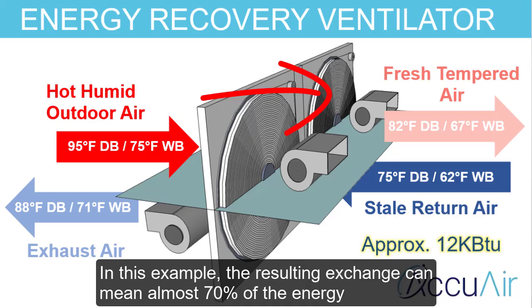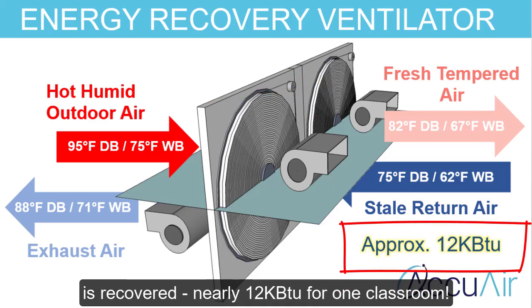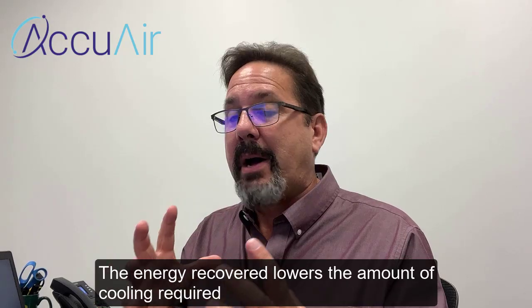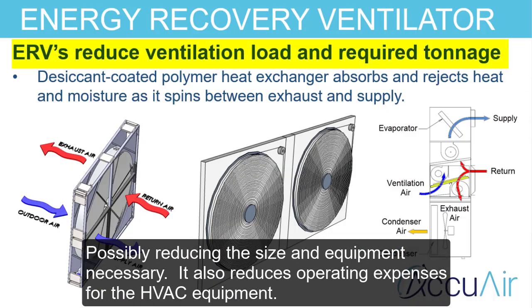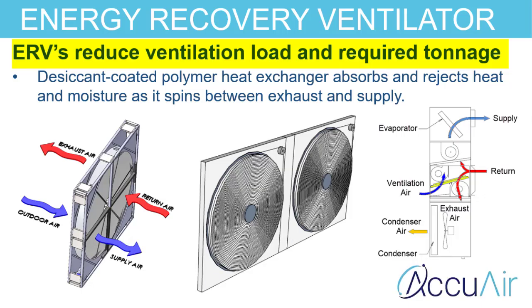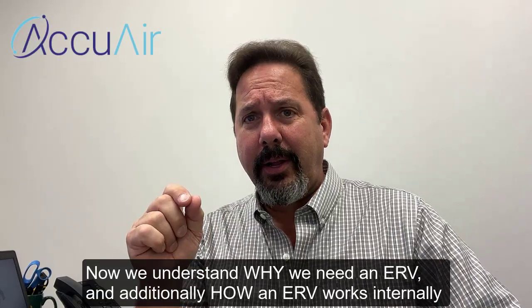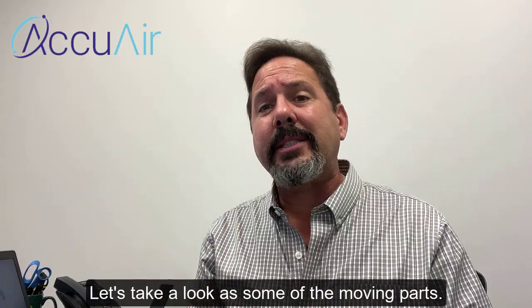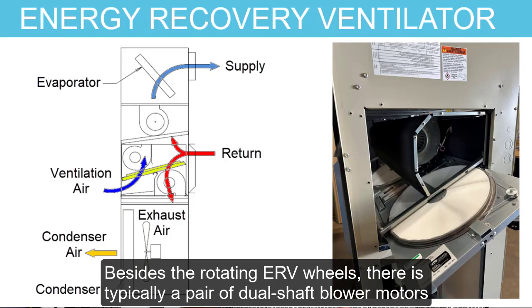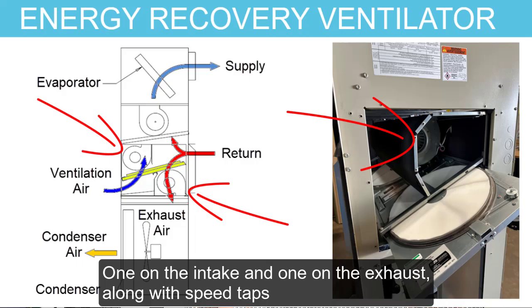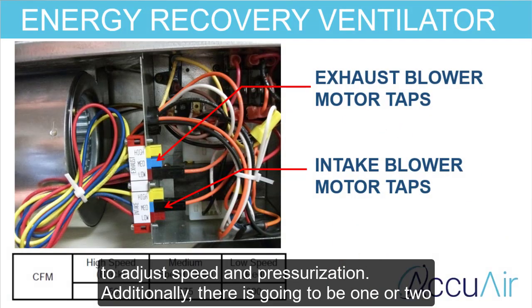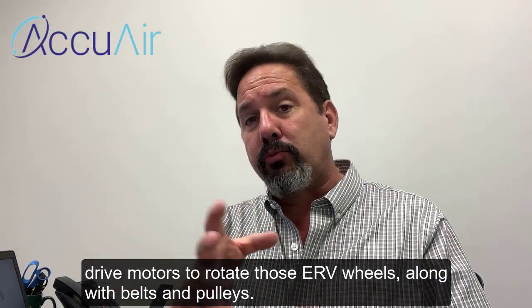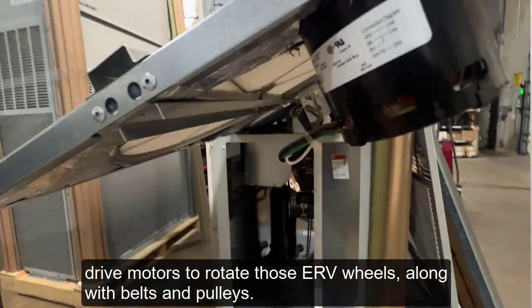In this example, the resulting exchange can mean almost 70% of the energy is recovered, nearly 12,000 BTUs for one classroom. The energy recovered lowers the amount of cooling required, possibly reducing the size of the equipment necessary, and also reduces operating expenses for the HVAC equipment. So now we understand why we need an ERV, and additionally how an ERV works internally. Let's take a look at some of the moving parts. Besides the rotating ERV wheels, there is typically a pair of dual shaft blower motors, one on the intake and one on the exhaust, along with speed taps to adjust speed and pressurization. Additionally, there's going to be 1 or 2 drive motors to rotate those ERV wheels, along with belts and pulleys.